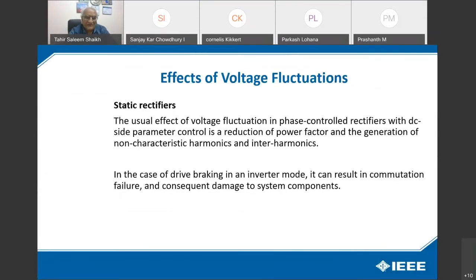Static rectifier. The usual effect of voltage fluctuation on a phase control rectifier with DC side parameter control is a reduction of power factor and the generation of non-characteristic harmonics and interharmonics. They come to it later on. In the case of a drive braking in inverter mode, it can result in commutation failure and consequent damage to the system components.